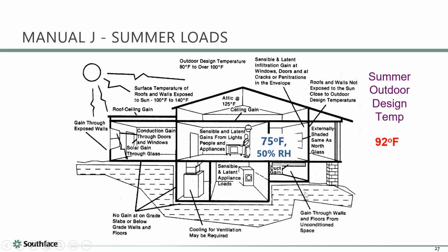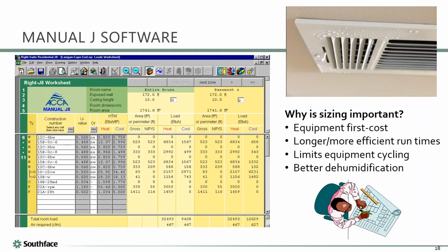So a cooling load is a little more complicated. And again, it's the almost hottest day of the year, but it's not the hottest day of the year. It's statistically the almost hottest time of the year. So that's going to be our process. And again, we'll add the loads from each room, and that will give us the total load, both sensible and latent. Today, we typically are using software to do this.